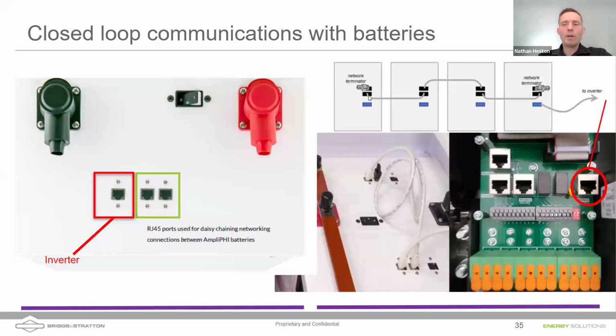Let's keep going because I have a few more topics I want to get through with everyone. When you are doing closed loop communications with our batteries, there are 3 different ports on the top of our communicating batteries. One of those ports is labeled device, and it's to go to the inverter. So this port that I'm highlighting that stands off by itself is the device port, which gets connected by one battery. You only need to connect one battery to the Sol-Ark 15k inverter.